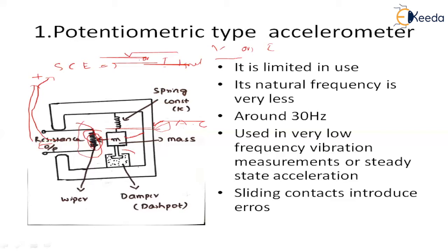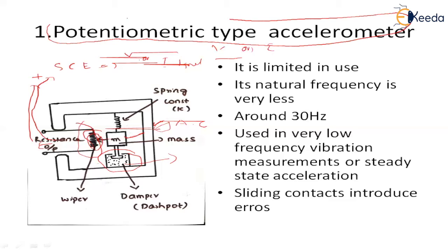A damper is used here. Damping is provided either by filling the space with a viscous liquid or by using an oil dashpot. This potentiometric type accelerometer is simple in construction. However, it is limited in use because its natural frequency is very low — around 30 Hz only. For this reason, it is used only in low frequency vibration measurements.